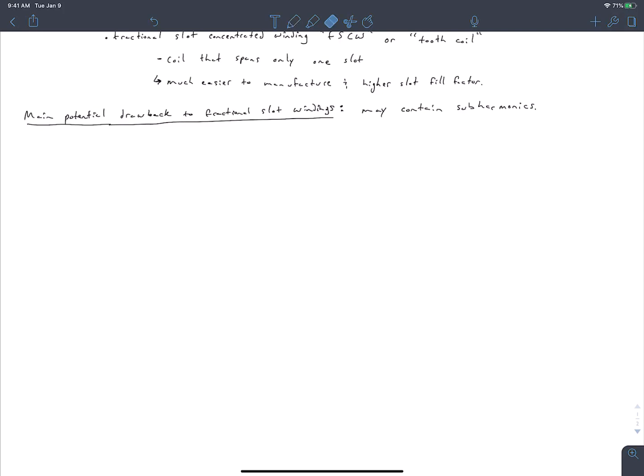I want to compare two example windings. One is a stator with 24 slots and 8 poles in a 3-phase motor, which gives a value of 1 slot per pole per phase — an integral slot winding. The second is a stator with 18 slots, 8 poles, and 3 phases, giving 3/4 of a slot per pole per phase. We'll draw this out, starting with the first winding: 24 slots, 8 poles, 3 phases.